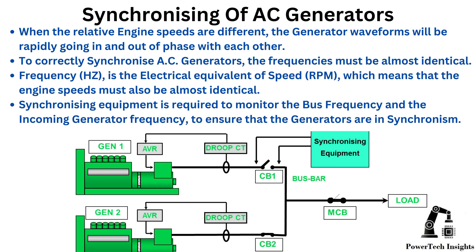When the relative engine speeds are different, the generator waveforms will be rapidly going in and out of phase with each other. To correctly synchronize AC generators, the frequencies must be almost identical. Frequency is the electrical equivalent of speed, which means that the engine speeds must also be almost identical. Synchronizing equipment is required to monitor the bus frequency and the incoming generator frequency to ensure that the generators are in synchronization.